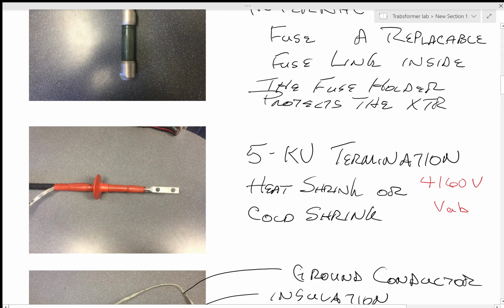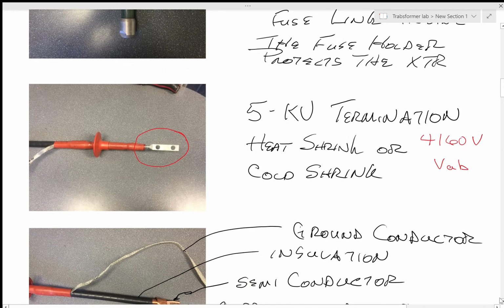Remember, everybody talks about line voltages. They don't talk about phase voltages. They talk about VAB, line voltages. That's the assumption. That's always the assumption. Notice that here, this bolts up to the spade lug. There's always going to be a lug on the transformer or the switch, and this end is going to bolt up to it. It's kind of like a terminator. It's like an elbow, but this is more like an original stress cone, which nobody makes anymore.